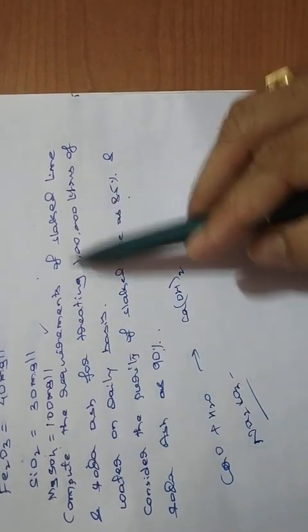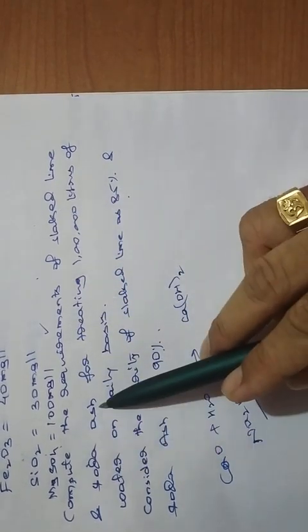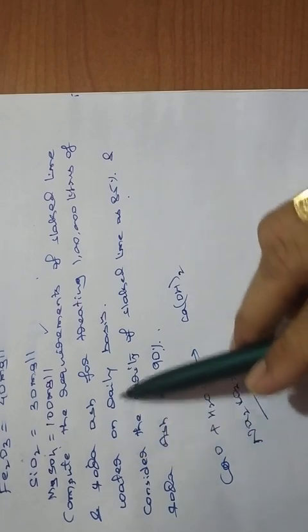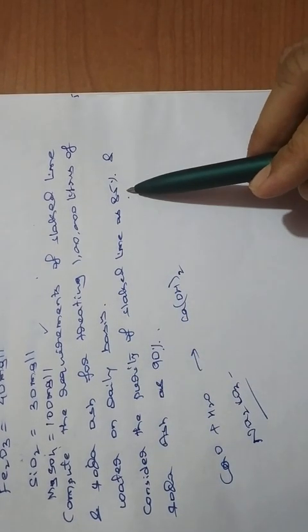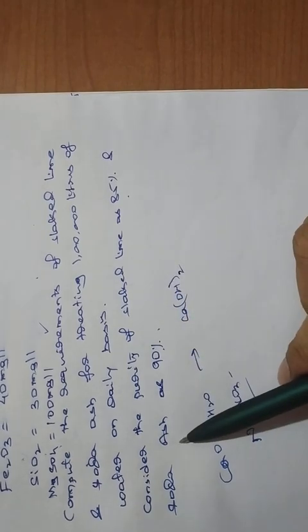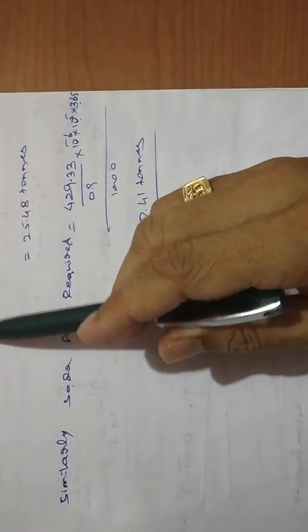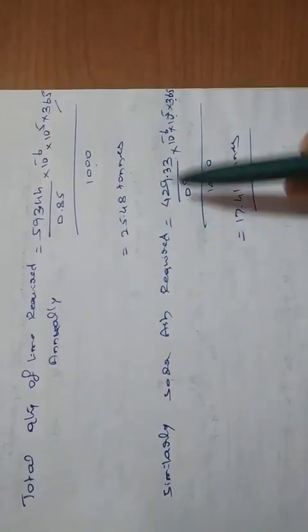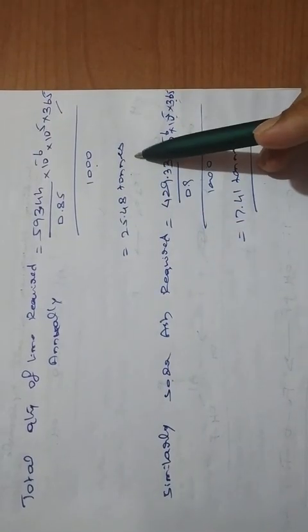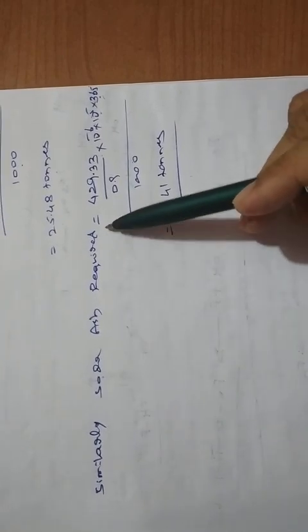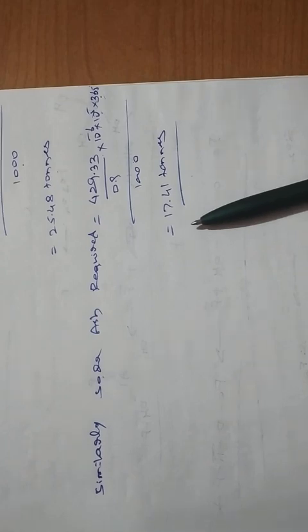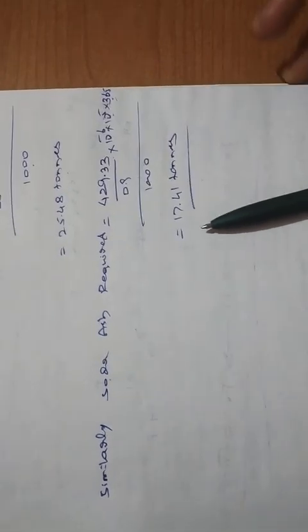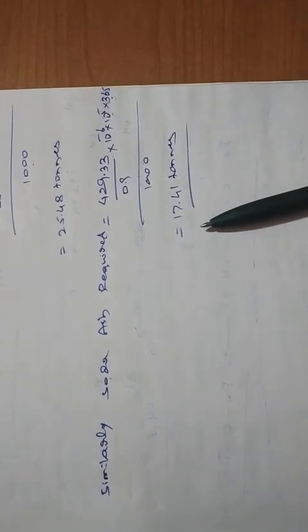To summarize: compute the requirements of slaked lime and soda ash for treating 1 lakh liters of water daily, considering 85% purity of lime and 90% purity of soda ash. The total quantity of lime required annually is 25.48 tons. The total soda ash required annually is 17.41 tons. Thank you.